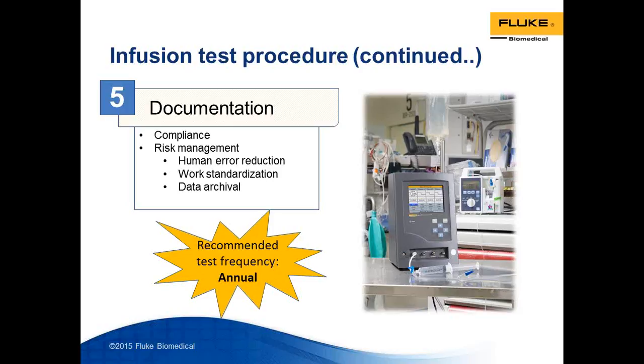And finally, the piece that is often overlooked but is extremely important is documentation. How do you actually document what you did? This ties right into compliance, whether it is regulatory compliance or your organization's methods in terms of tracking that everything is done as specified by the end users. This also ties into risk management, and there are a number of elements when it comes to risk management. When you document the work you did and show that it was done during the time it was supposed to be done, and everything was checked off and the pump was okay, you are essentially making sure that in case there is ever traceability required, you have that data readily available to you.